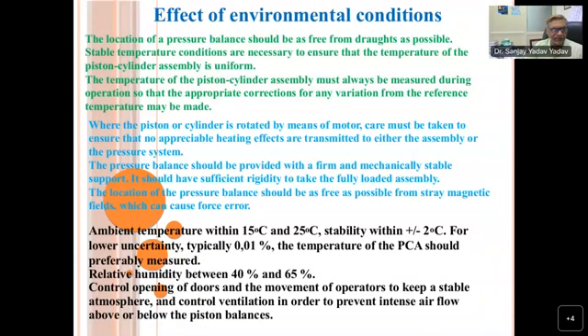So, effect of environmental conditions. The location of the pressure balance should be free from draught as much as possible. Stable temperature conditions are necessary to ensure that the temperature of the piston cylinder assembly is uniform. The temperature of the piston assembly must always be measured during the operation so that appropriate correction can be made for any variation from the reference temperature. Ambient temperature within plus minus, between 15 and 25 degrees centigrade with stability plus minus 2 degrees centigrade. This is a standard document, OIML. For lower uncertainty, typically 0.01%, at the temperature of the PCA. Relative humidity between 40 and 65. Control opening of doors and movement of operators to keep a stable atmosphere. Control ventilation in order to prevent intense airflow.